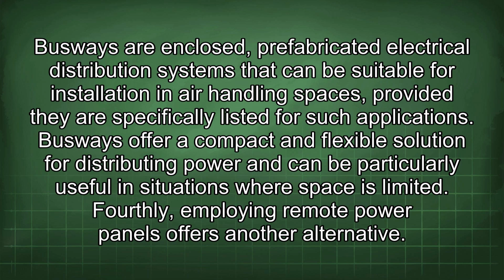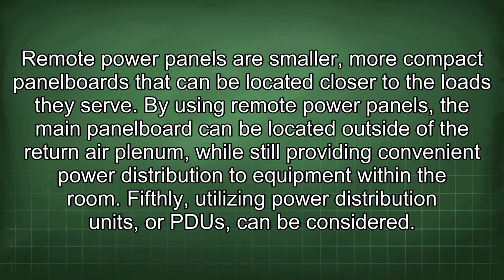Fourthly, employing remote power panels offers another alternative. Remote power panels are smaller, more compact panel boards that can be located closer to the loads they serve. By using remote power panels, the main panel board can be located outside of the return air plenum while still providing convenient power distribution to equipment within the room.